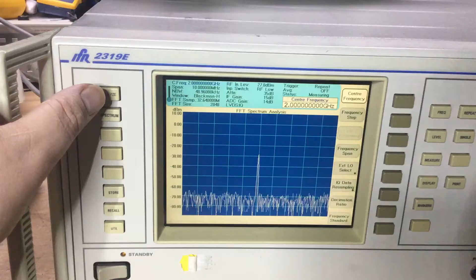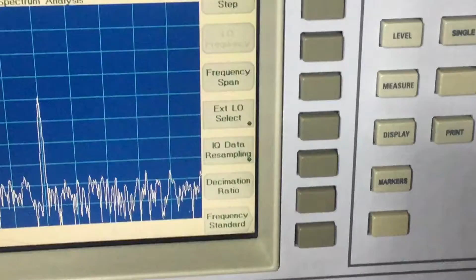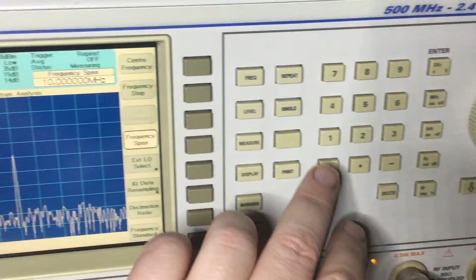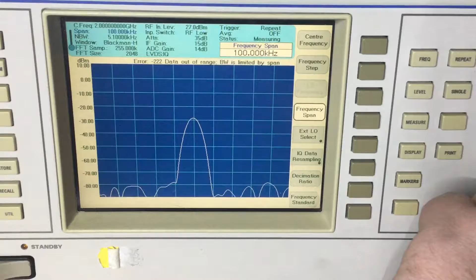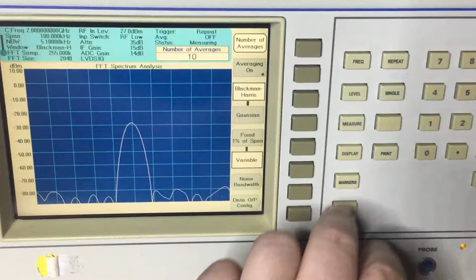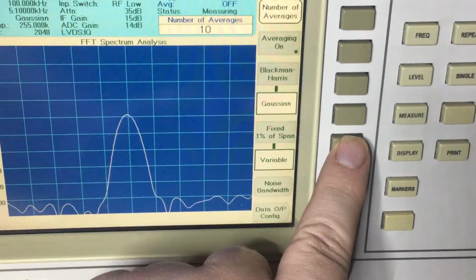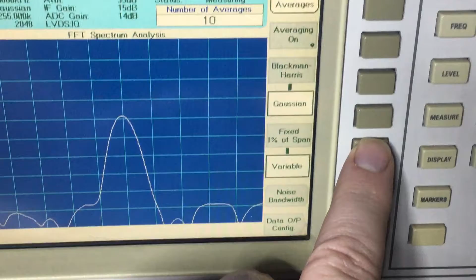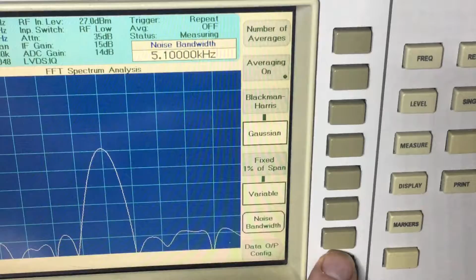And then under the analyze function, you can go into further detail. And obviously there's quite a lot of menus as well down here. IQ data, frequency span, so you can adjust the frequency span to say, I don't know, 100 kilohertz in this case. And then you can look at the signal in more depth that we're injecting in. There's the measure, and then down here we've got Blackman Harris, N filters and things like that we can select. All sorts of different filters. Gaussian filter obviously for GMSK or GSM modulation, fixed 1%, variable, so many things there under that measuring.